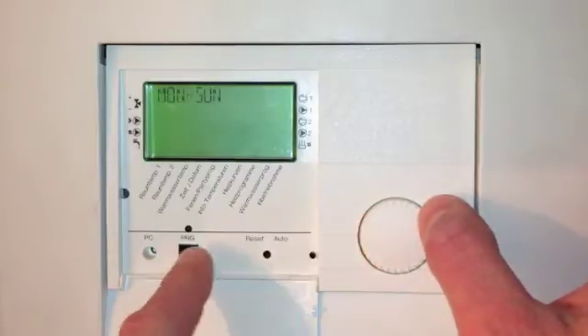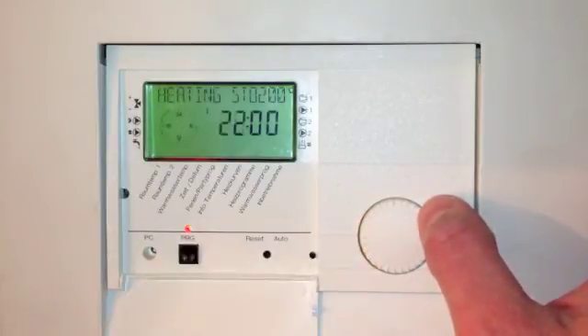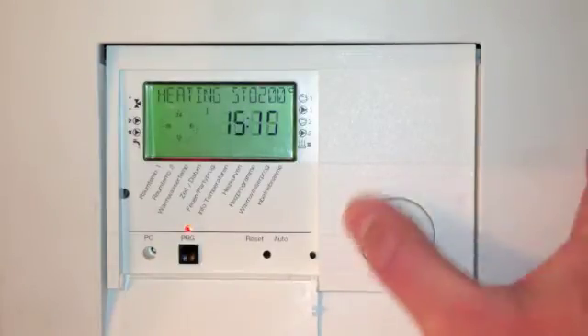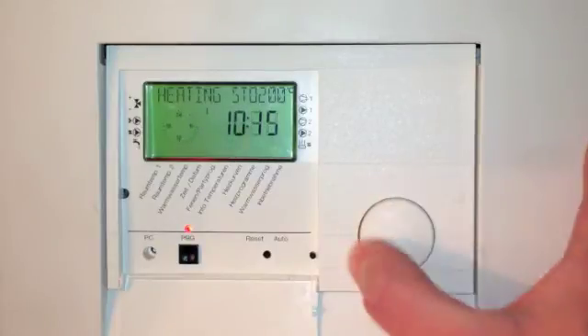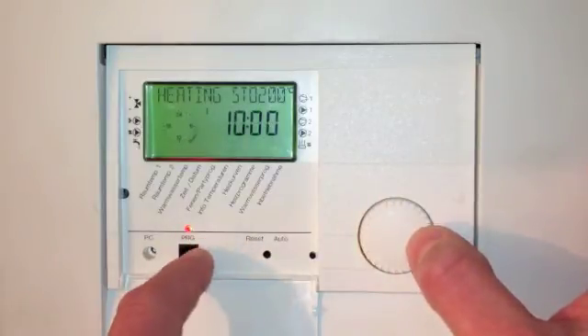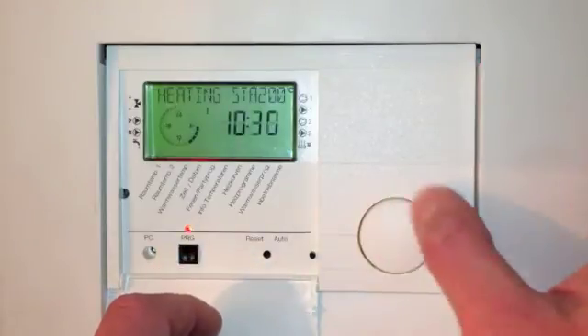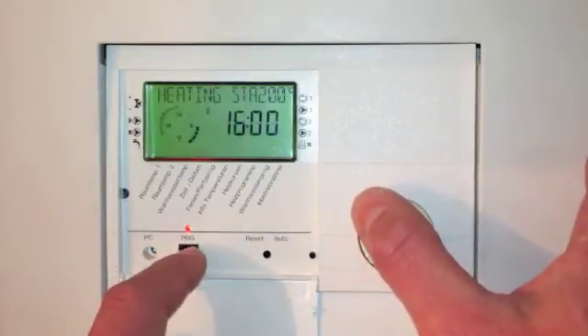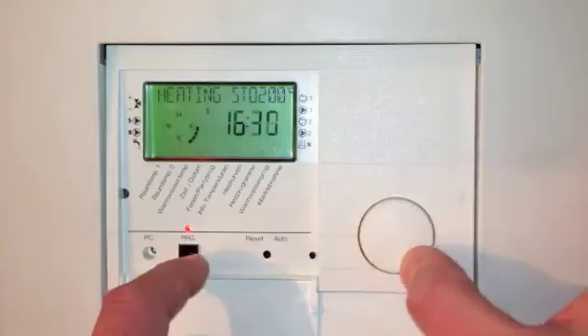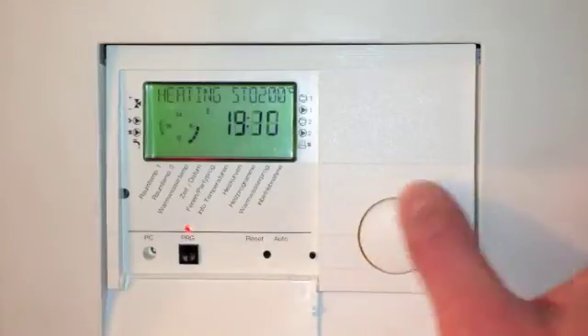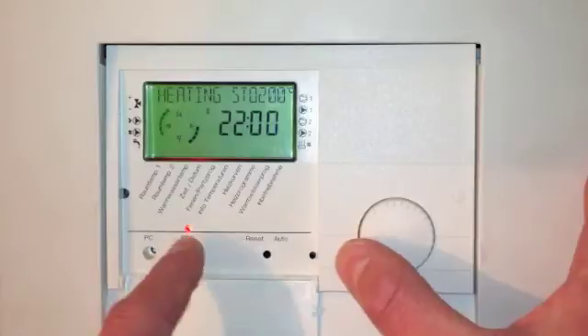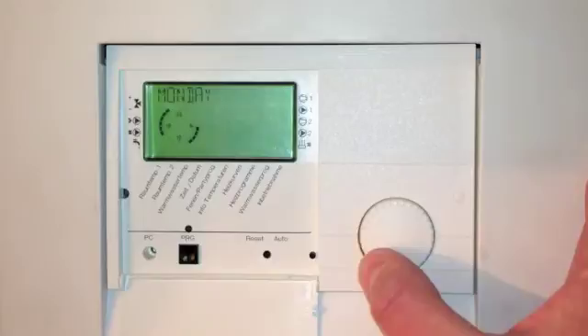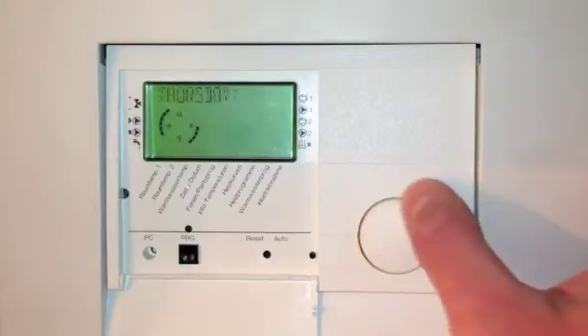You can alter the days individually or all together. I'm going to alter them all together on the Monday to Sunday setting. At the moment it's set from 6 in the morning till 10 at night. I'm going to change that from 6 in the morning till 10 in the morning on the day setting, and then from 4 in the afternoon till 10 at night on the day setting as well. So between 6 and 10 we're set at 20 degrees, between 10 and 4 we're set down at 18, between 4 and 10 we're set back at 20 degrees, and then between 10 and 6 the following morning we're back down to 18.